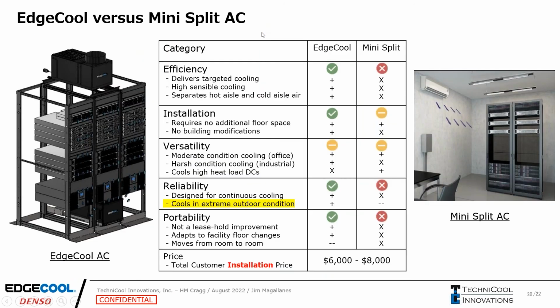How we stack up to mini split systems. We think mini split systems have the largest market share now. Efficiency wise, we're delivering targeted cooling, have high sensible cooling, and we're separating hot aisle and cold aisle air. So all these are a plus for EdgeCool. Mini split systems just don't work that way, so they're not really efficient that way. Installation, we're installed inside the room. We don't take up any additional floor space, and we're not doing any building modifications.